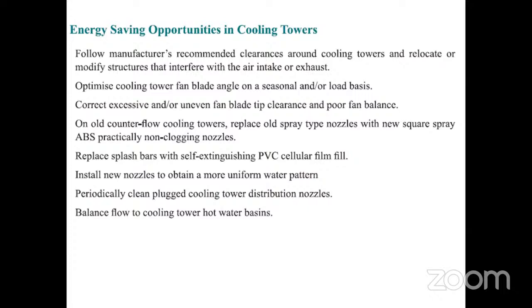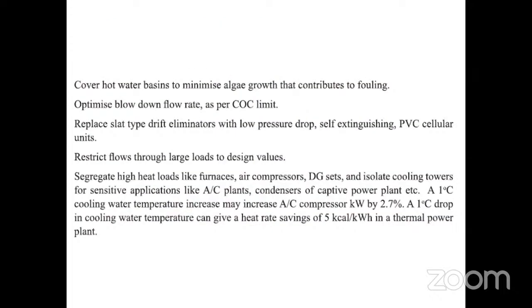Periodically clean plugged cooling tower distribution nozzles. Balance flow of cooling tower hot water basins. The hot water basin has to be covered, sir. It should not be open to the sun. Otherwise, there will be algae growth, which will contribute to fouling. Optimize blow down rate as per COC limit. If you blow down frequently, energy will be lost, water will be lost. So for optimum COC limit, we will be doing the blow down.